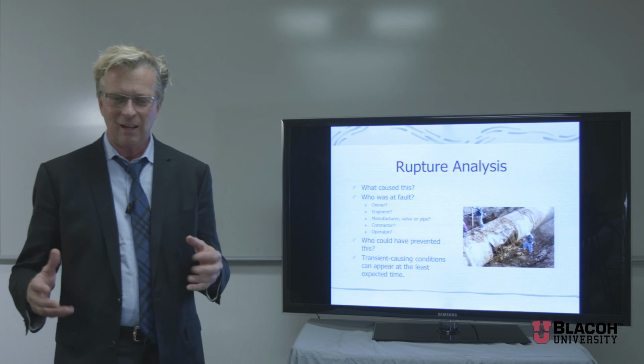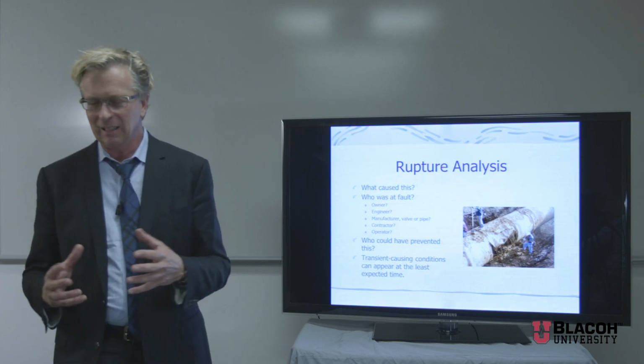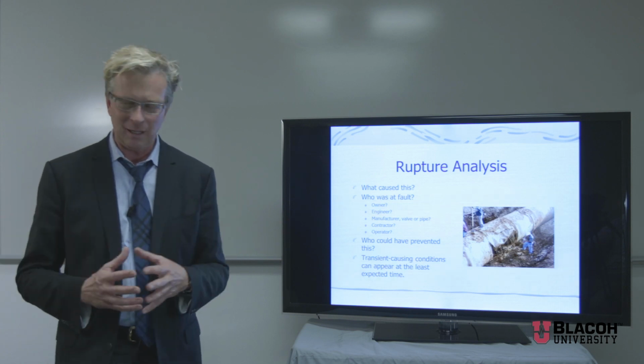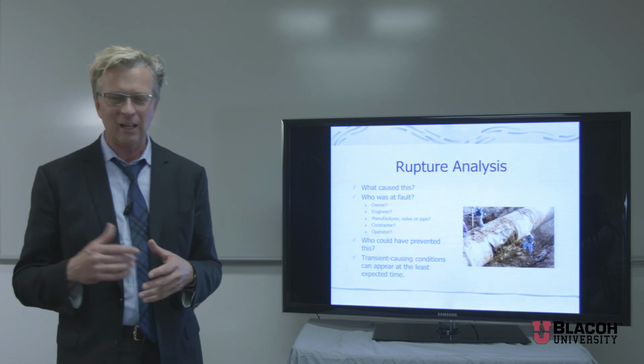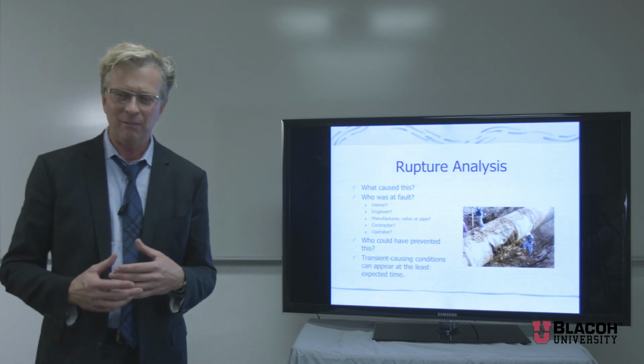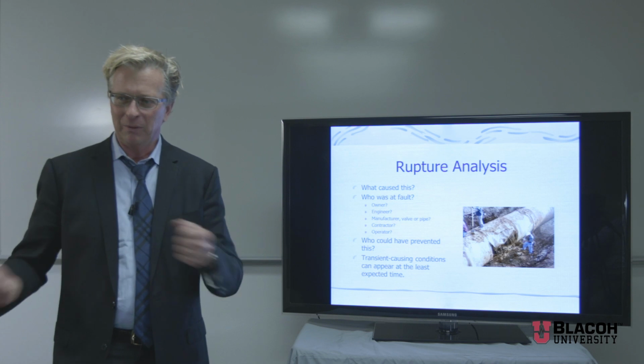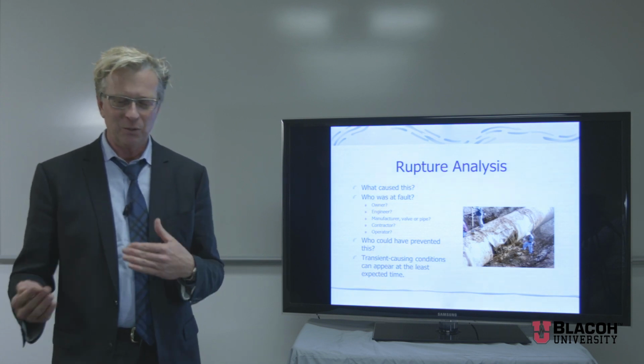And most jobs I go to, the contractor calls me up. It's like, I have this pipeline. I hydro tested the line, passed the pressure test, all is well. They turned on the pump, turned off the pump, and now all of a sudden they're telling me my pipeline's leaking. Whose fault is it? Well, the contractor's like, I have a perfect system, everything held. Now my pipe seals are all leaking, and the owner and the engineer aren't going to pay me. Well, the chain of events was they had a pump trip which sent out a negative wave into the piping system and moved the pipe or the seals, which now it's leaking.